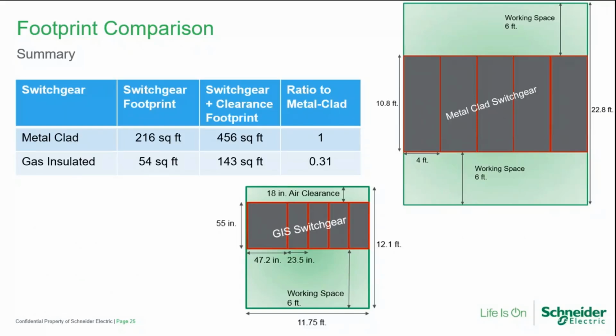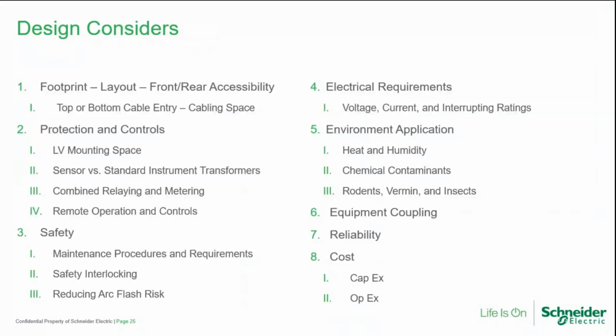I don't put an SIS example with this because the metal enclosed SIS designs I've seen so far only go up to 15 kV. So once we look at that 27, 38 kV options, we're looking at gas insulated switchgear only for those options. So some pretty big footprint savings. So I'm kind of getting to the end here of my presentation with a couple of minutes left for question and answer, which is great.